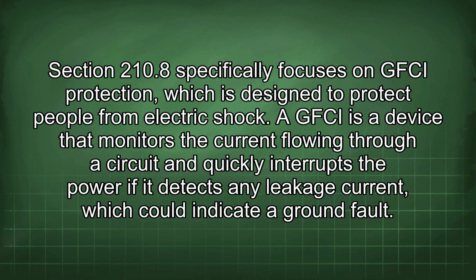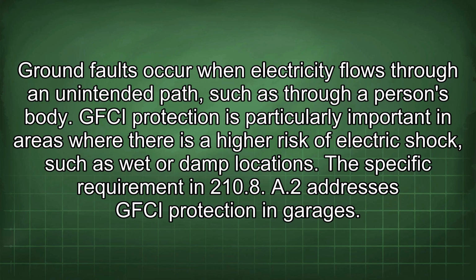Section 210.8 specifically focuses on GFCI protection, which is designed to protect people from electric shock. A GFCI is a device that monitors the current flowing through a circuit and quickly interrupts the power if it detects any leakage current, which could indicate a ground fault. Ground faults occur when electricity flows through an unintended path, such as through a person's body. GFCI protection is particularly important in areas where there is a higher risk of electric shock, such as wet or damp locations.